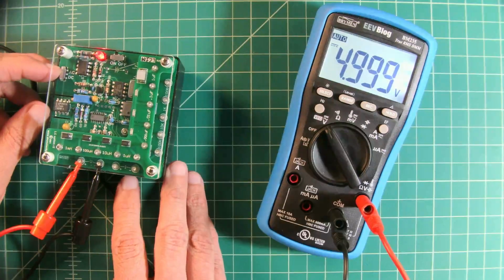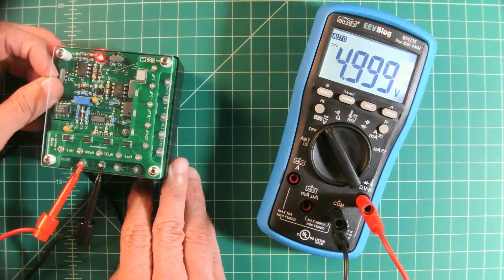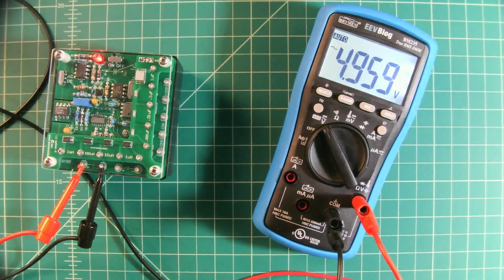Let's go ahead and change this to AC, see what we get. And here we go, we have 4.959, and according to the certificate, it would be 4.999. So we are okay with that as well.